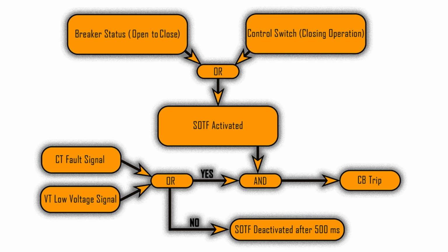On the other hand, if the SOTF relay is actuated but no fault signal comes from the CT and no low voltage signal comes from the VT, both are false, then the SOTF will be deactivated after 500 milliseconds and will reset, ready for the next operation.